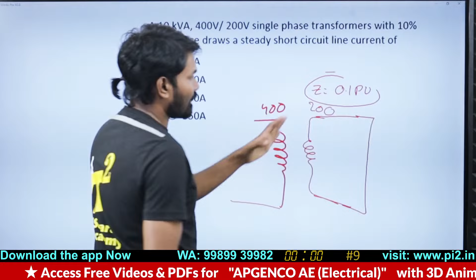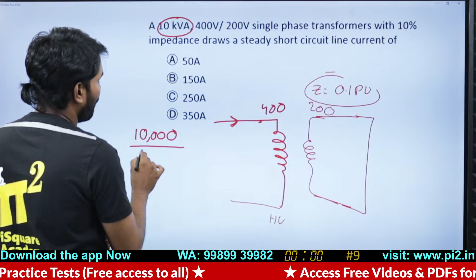Tell me, what is the rated current in the high voltage side? Rated current is, this is power S, apparent power 10,000 by 400. This is 25 ampere, am I right? Correct me if I'm wrong. Yes, this is 25 ampere. This is not a short circuit current, this is a rated current.